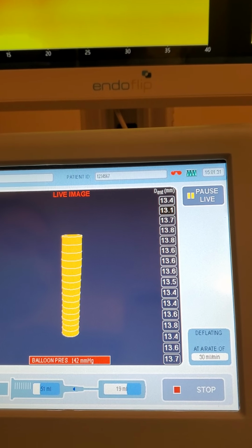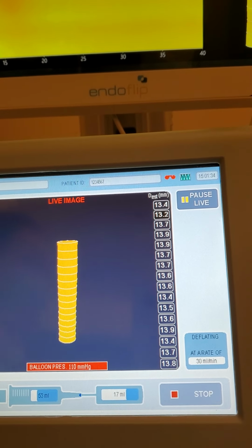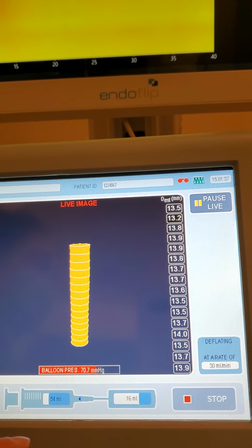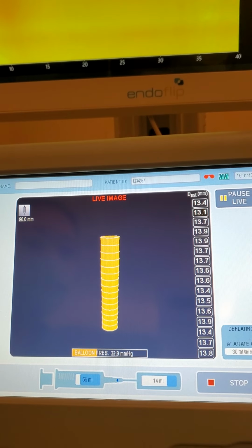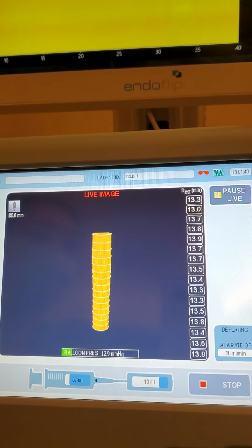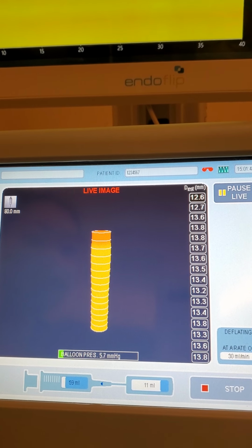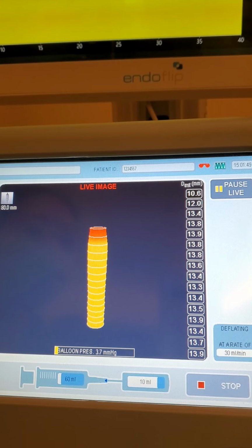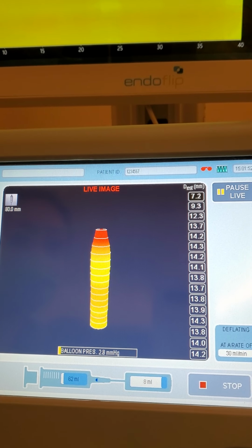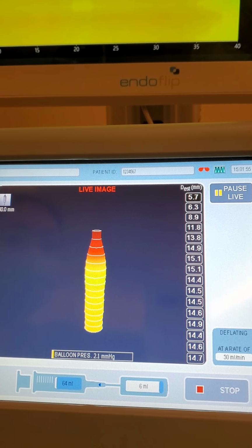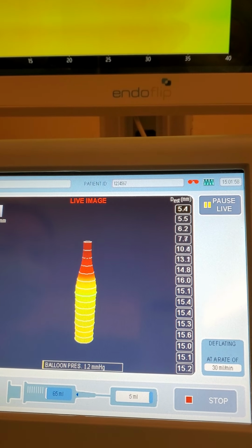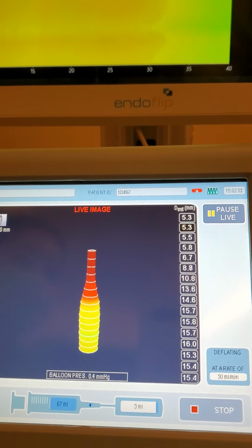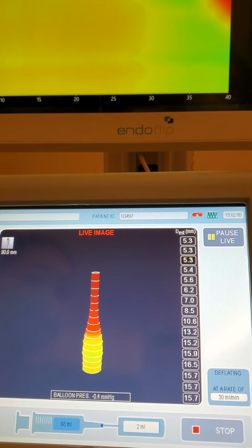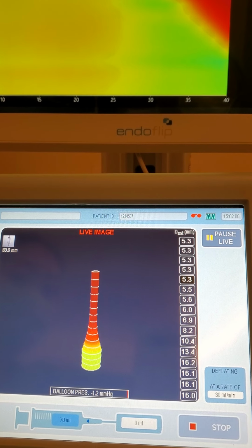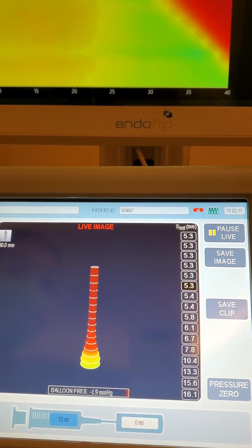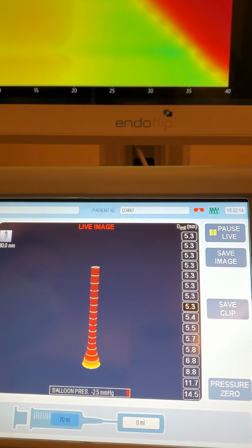So you press deflate. So in a normal case scenario, when you came back to the machine after it purged, you would see a message that says catheter ready for use, purge was successful. So let's say this was a normal case scenario. So it's going to deflate on its own. Deflation is pretty slow. Okay, so it's deflating. Sometimes it continues to pull liquid out even after the syringe is done.